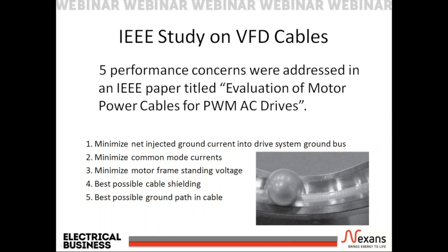Number 3, minimize motor frame standing voltage. This also reduces the possibility of bearing currents, but also increases safety. Motor frame standing voltage can present a shock hazard or a source of ignition in hazardous locations. Number 4, best possible cable shielding. This will help reduce the likelihood of crosstalk between adjacent cables, either inbound or outbound, and reduce the possibility of interference with wired or wireless systems.